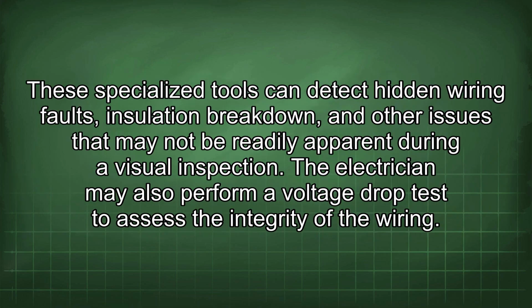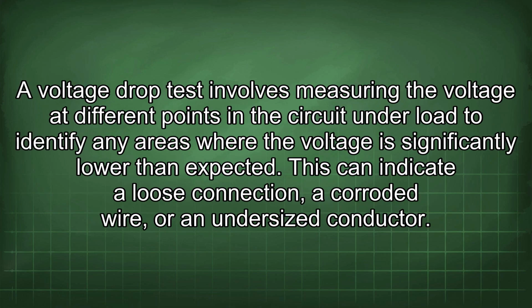These specialized tools can detect hidden wiring faults, insulation breakdown, and other issues that may not be readily apparent during a visual inspection. The electrician may also perform a voltage drop test to assess the integrity of the wiring. A voltage drop test involves measuring the voltage at different points in the circuit under load to identify any areas where the voltage is significantly lower than expected. This can indicate a loose connection, a corroded wire, or an undersized conductor.